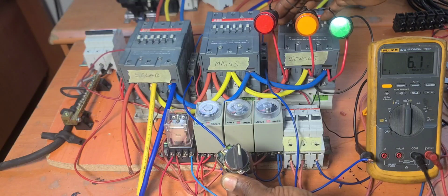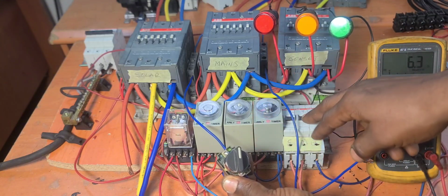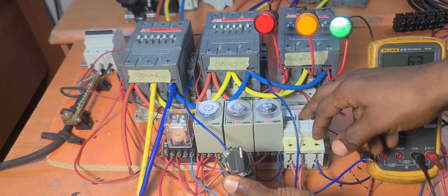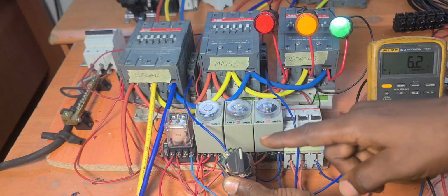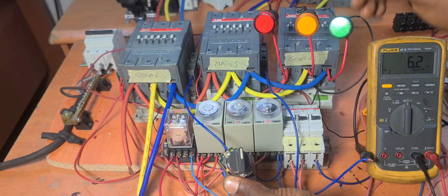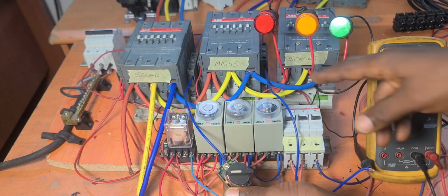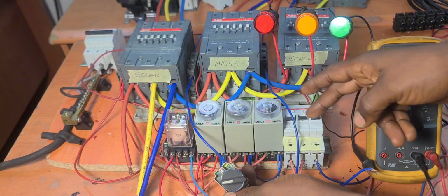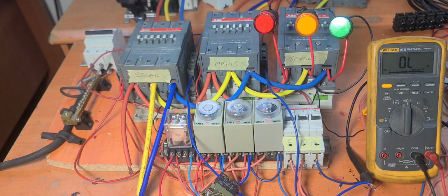Please, I need you to know the difference. There is a difference between the signal that starts the generator and the power that comes from the generator. So with this continuous beep, it means that the generator is in automatic mode, is going to start by itself. And for us to put it on manual mode, we're going to open this place, so we don't need to short this cable anymore, and that signal to start the generator is not going to go there.